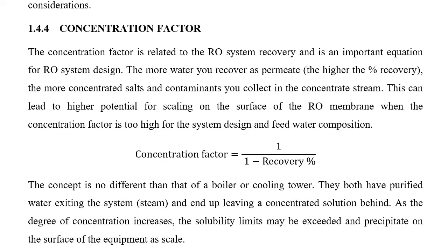So on the raw water side there will be less water left, but the salt concentration will be very high. So the formula to calculate concentration factor is equal to 1 by 1 minus recovery percentage.